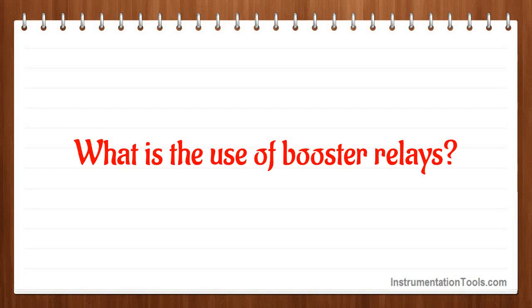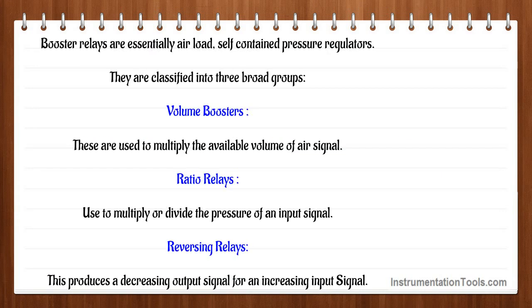What is the use of booster relays? Booster relays are essentially air-loaded, self-contained pressure regulators. They are classified into three broad groups: volume boosters, which are used to multiply the available volume of air signal; ratio relays, used to multiply or divide the pressure of an input signal; and reversing relays, which produce a decreasing output signal for an increasing input signal.